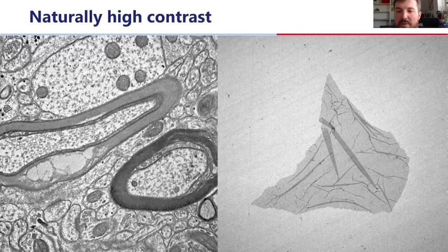And the explanation comes directly from physics. Slow electrons are scattered much more strongly than fast ones. While high-energy electrons pass through the sample almost unnoticed, low-energy, slow electrons have much more time to collect more information on their way through the sample. A direct consequence of this property is that we can reduce or even completely eliminate staining. And even without staining, we can still achieve results comparable to those from conventional TEMs with fully stained samples.